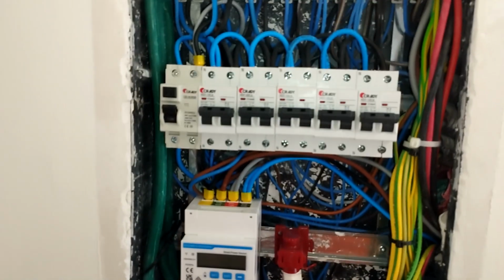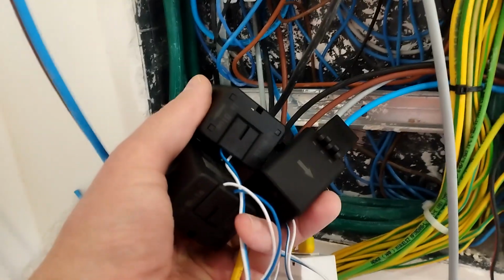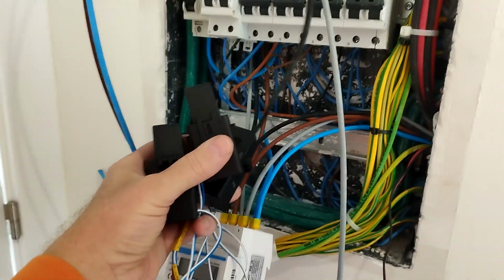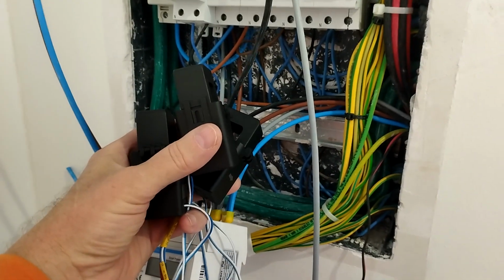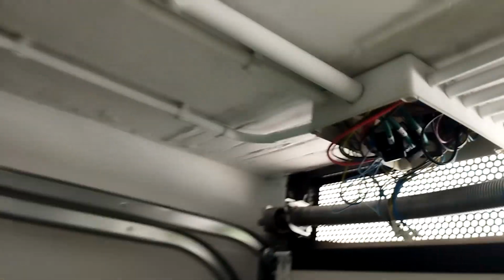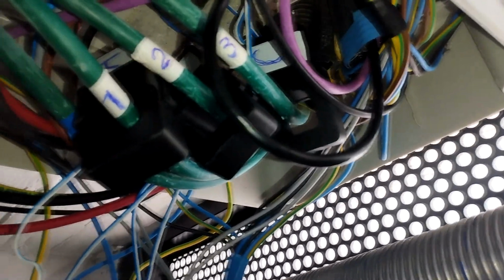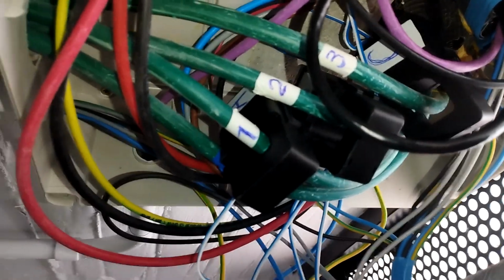However, there is one major problem. The smart meter kit includes 3 current transformers, CTs, one for each phase, which must be installed on the incoming supply cables that feed the house. Normally, we install these CTs inside the main distribution board, in front of the main automatic circuit breaker. But here, there is absolutely no space, and CTs are quite large. Fortunately, we found suitable space in the basement. The incoming cables are accessible there, and there is enough room. This is a junction box on the basement ceiling, located directly beneath the main distribution board.